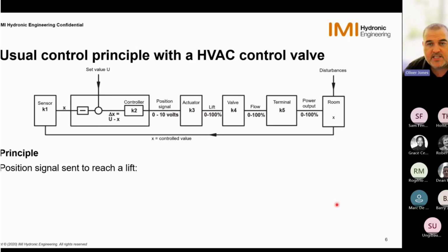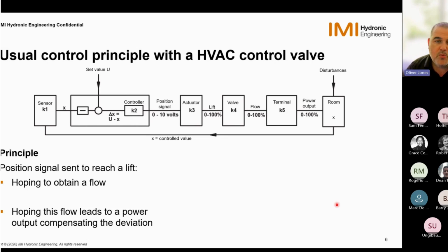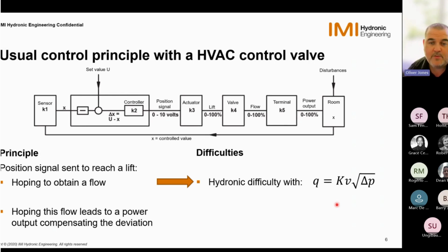So the general principle is that we send a position signal to reach a lift. That's what we do out of the controller, and then from this lift we hope we'll get a flow. But will we get the flow that we believe we would get according to the different curves and properties of the components? Well, probably not, because there are certain challenges. There is the hydronic network, where there are delta P variations and other things impacting the possibility to obtain a certain flow. We hope that flow will give us a thermal output, and that will help us to compensate for the deviation in the room.